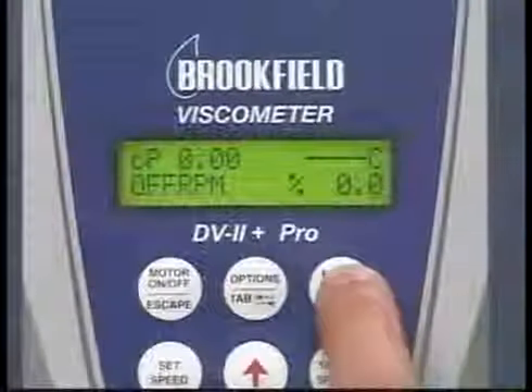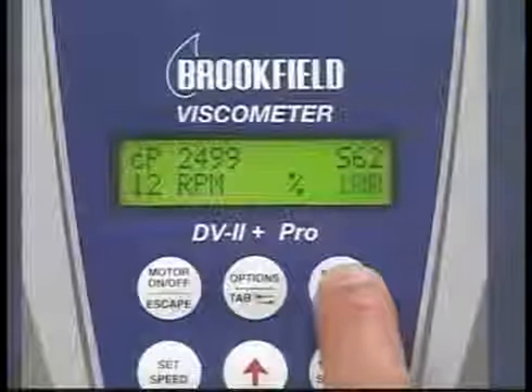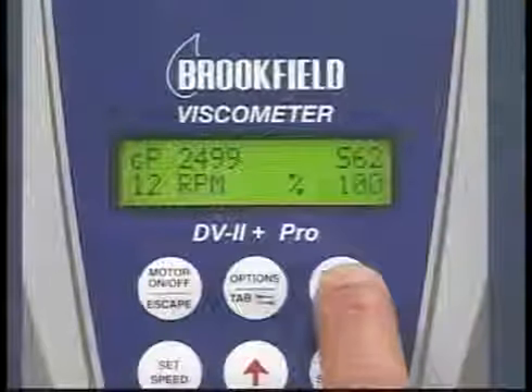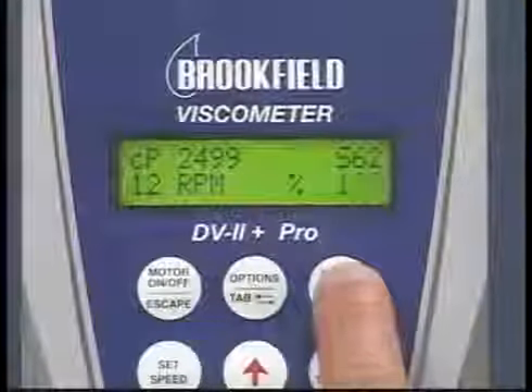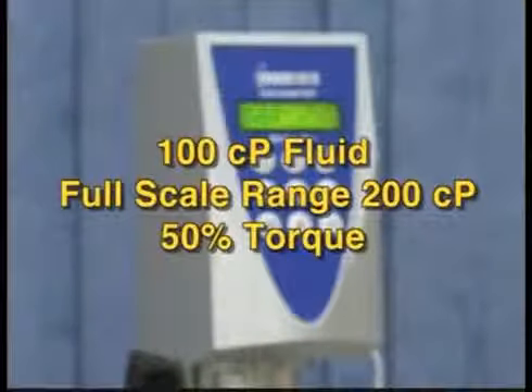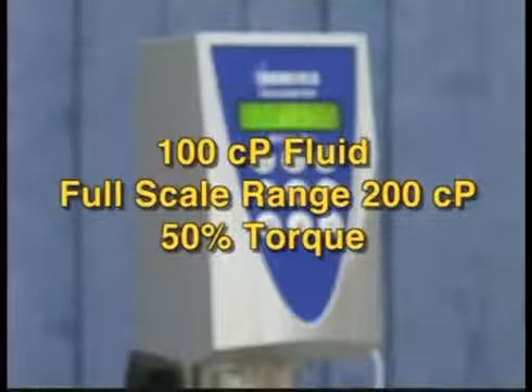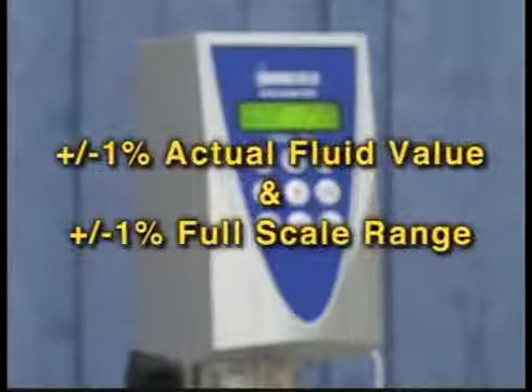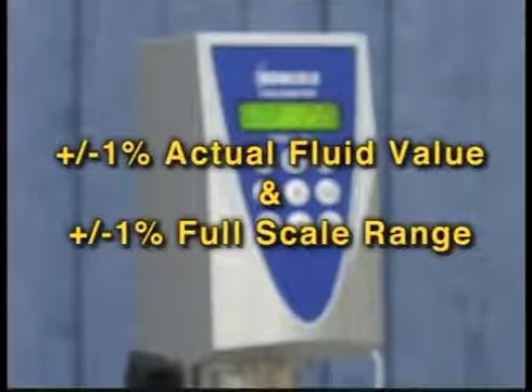With the digital instrument, you can easily find the full scale range by turning on the motor and pressing and holding the auto range button. For example, if you have a 100 centipoise fluid, a full scale range of 200 centipoise will give you 50% torque. Tolerances for calibration are computed using plus or minus 1% of the actual fluid value and plus or minus 1% of the full scale range.